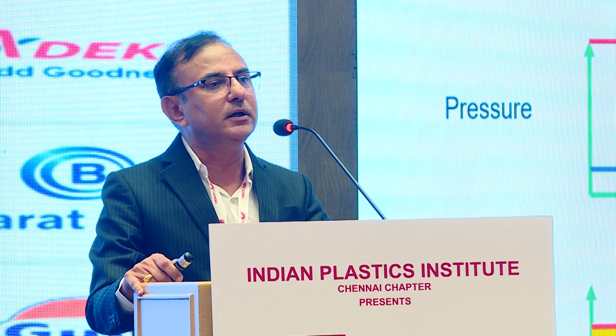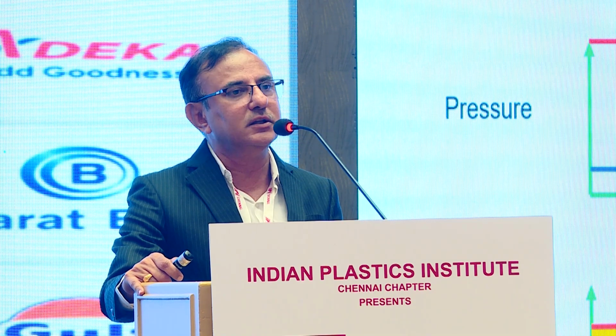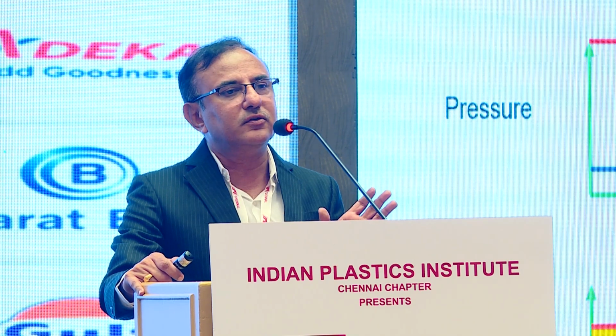As you can see, in servo technology, we are pumping the oil only when it is required. Under the idle condition, we are bringing the speed of the pump and the motor close to 0. So what is energy? That is a product of flow and pressure. So we are pumping the oil only when it is required. In idle condition, we are not pumping any oil. So that is how we are able to get the energy saving using the servo technology.